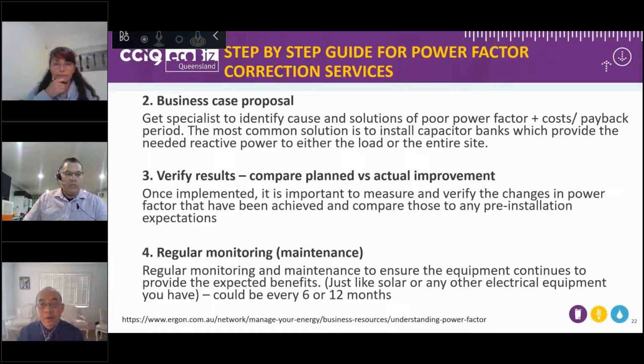So once you've worked out what your current power factor is, and if you see that your power factor is below 0.95 or even below 0.9, then get a specialist to come in and do a business case proposal, working out what your investment in power factor equipment is, and working out the payback depending on the reduced kVA and the bill impact. So the most common solution, as Phil mentioned, is to install capacitor banks, which will help improve the power factor.